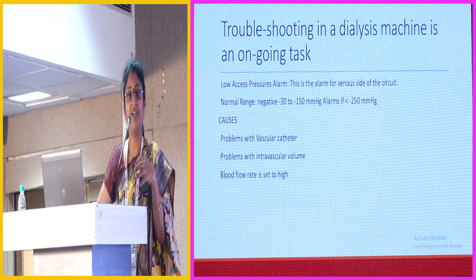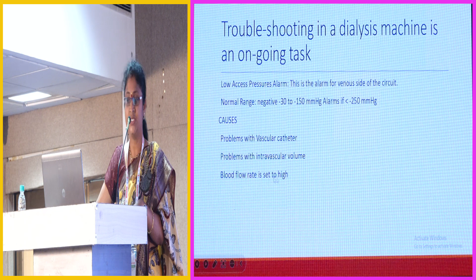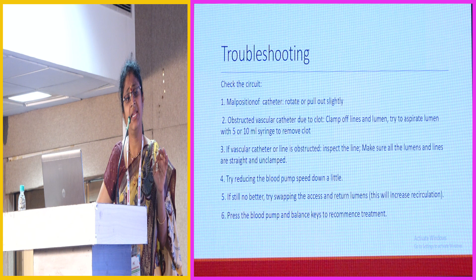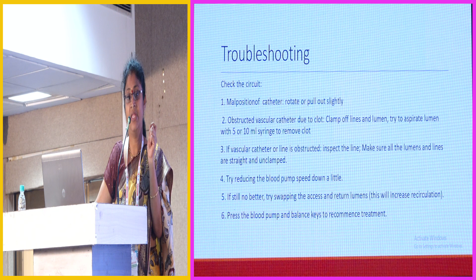Next are problems with intravascular volume. Suppose the patient is very hypotensive and you set very high blood flow rates, at that time also you get this low venous pressure alarm. So how do you fix that? For malposition of the catheter, rotate or pull out slightly. If you see an obstructed vascular catheter, try to aspirate and remove the clot. One more thing: whenever you get any alarm, try to see the clamps. Anywhere we may forget to release a clamp. If there is any clamping across the circuit, try reducing the blood pump speed down a little.